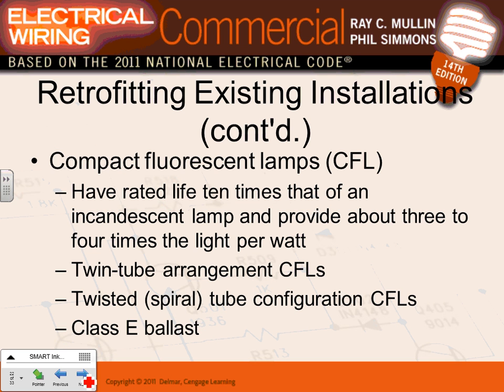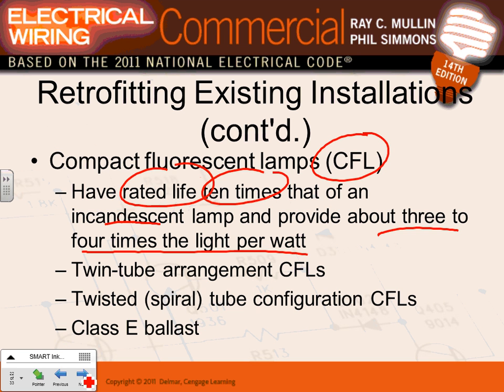Then we have compact fluorescent, the ones I put in my house. These are the compact fluorescent. The nice thing about the compact fluorescent, guys, is they can replace the incandescent lamps, right? Anywhere, supposedly. Rated life is higher. I start questioning them. Rated life is 10 times higher than their counterparts, the incandescent lamps, and they can produce 3 to 4 times more lumens, more light or lumens per watt, which is great. So they're more efficient and they live longer. Who doesn't want a car that's more efficient and lives longer? Or a lamp that's more efficient and lives longer? My personal experience with them, I changed all my house with them, as I said.